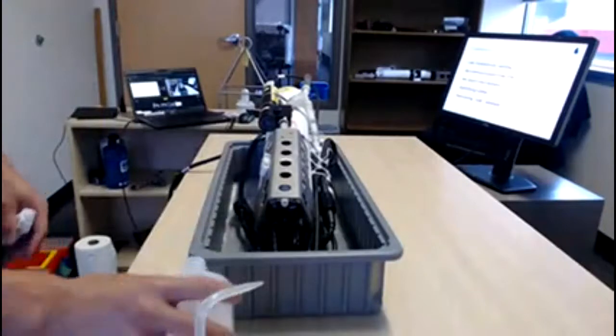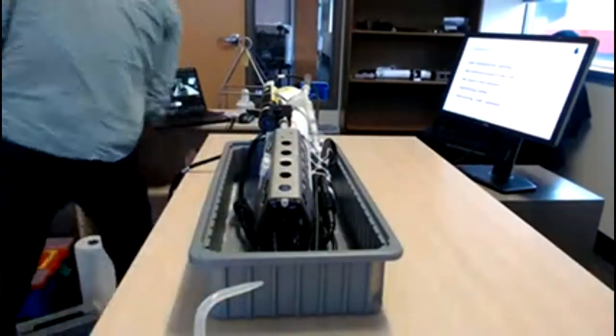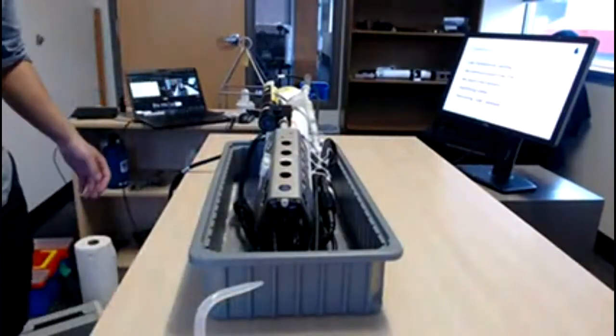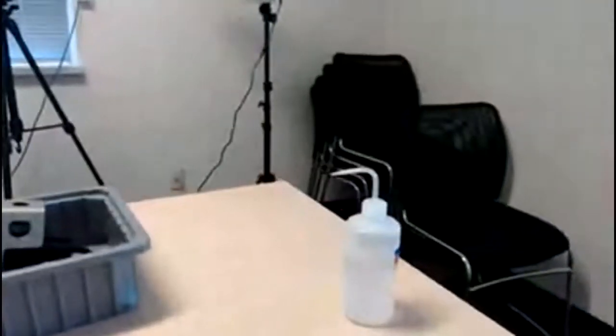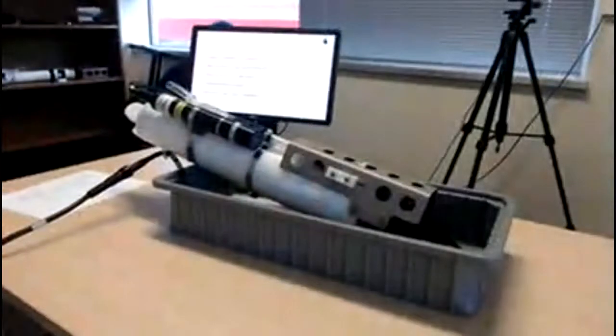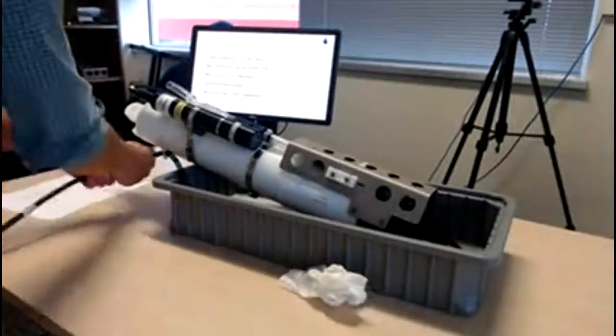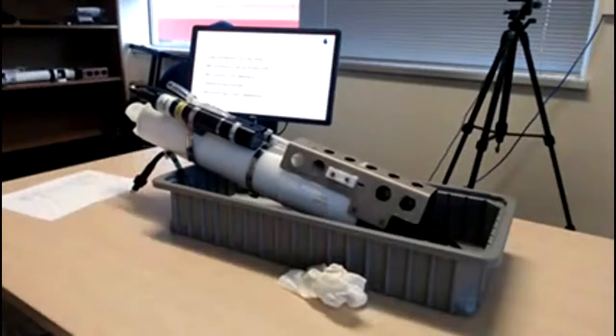Okay, next we have this problem where you might have no communication from your CTD. And in that case, it's useful to run what we call the loop back test. Now, this test is to determine whether or not the cable you have connected to your CTD, the data I/O cable I've got right here, is actually sending data to CTerm. That will ensure, if it passes, that you have the correct COM ports and your cable actually works. So what you can do is pull out your cable.